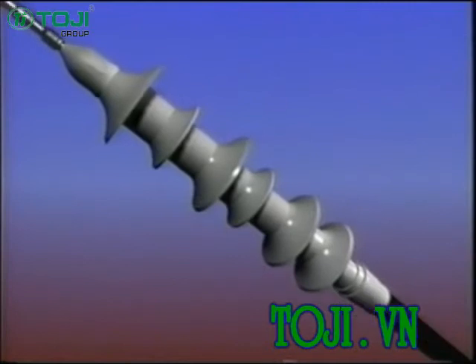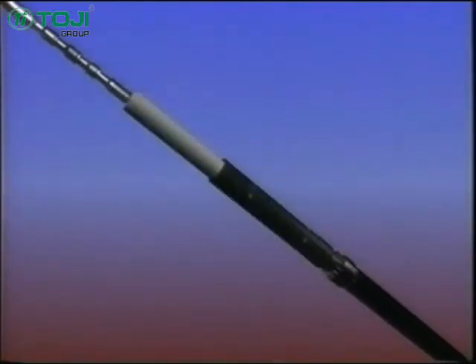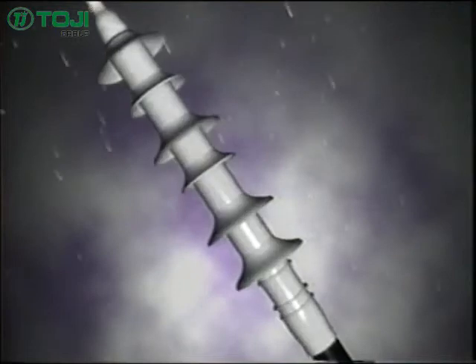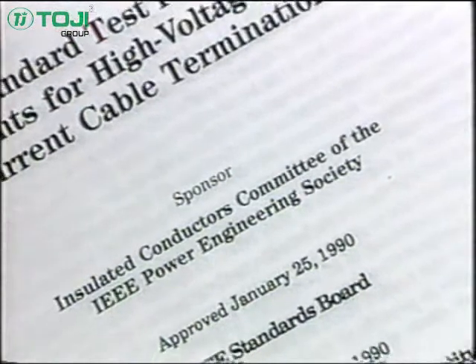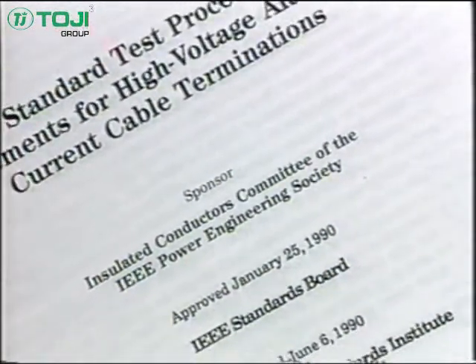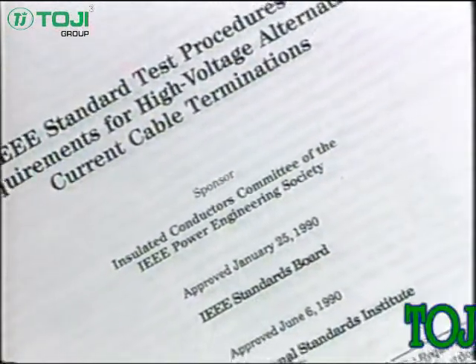The high K stress relief inside the termination relieves the electrical stress at the end of the cutoff cable shield and evenly distributes the electric field over the cable end, thus allowing for shorter, more compact terminations. Silicone rubber insulators are the best, most protective material, providing stable, reliable performance in the harshest environments over the life of the product. According to the IEEE 48 1990 standard, a Class 1 termination must meet 3 criteria.